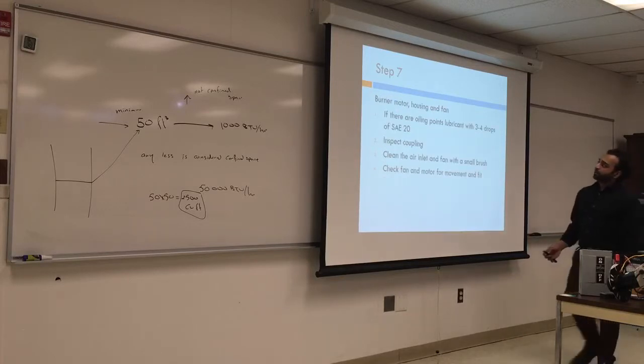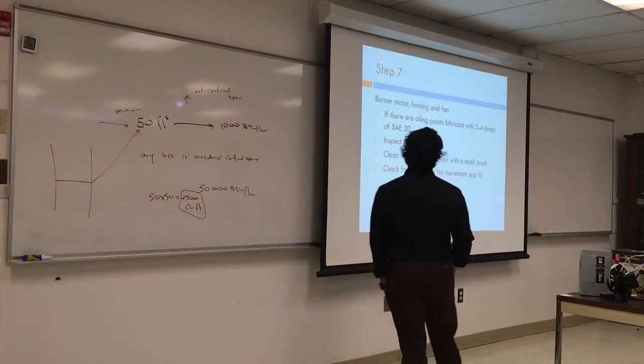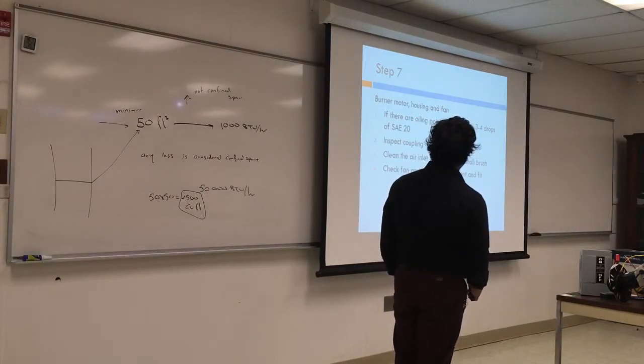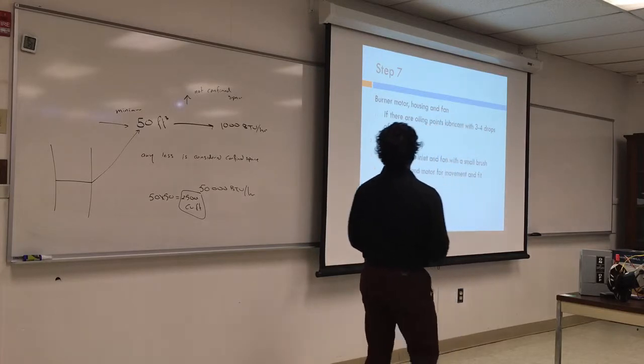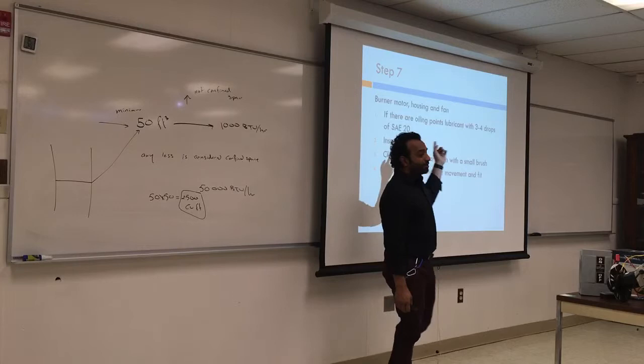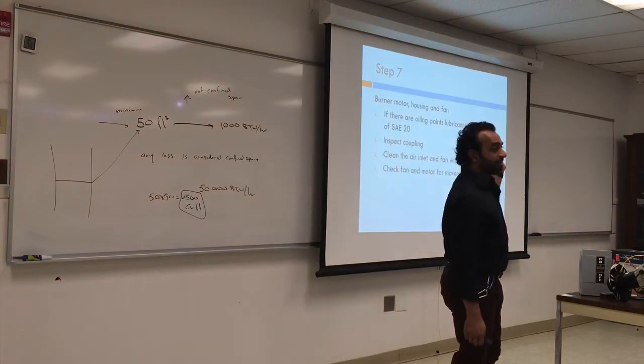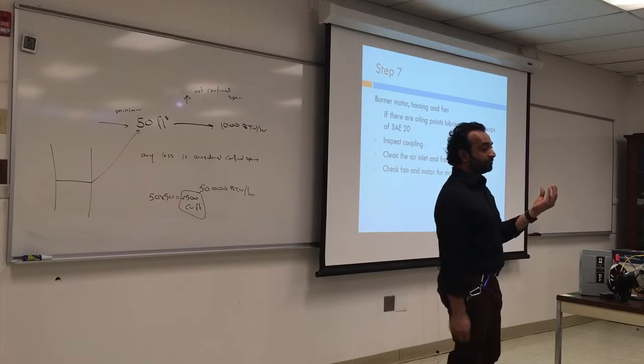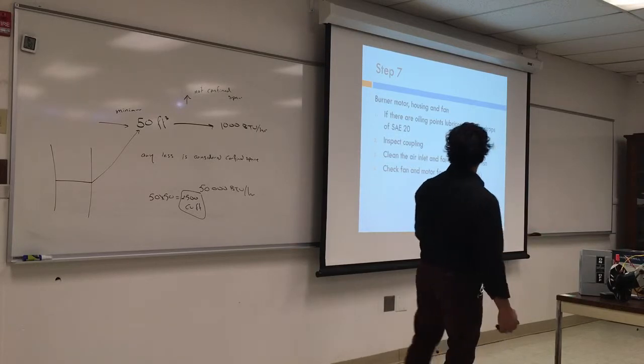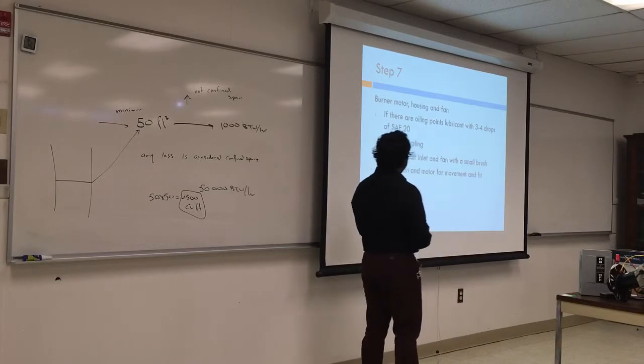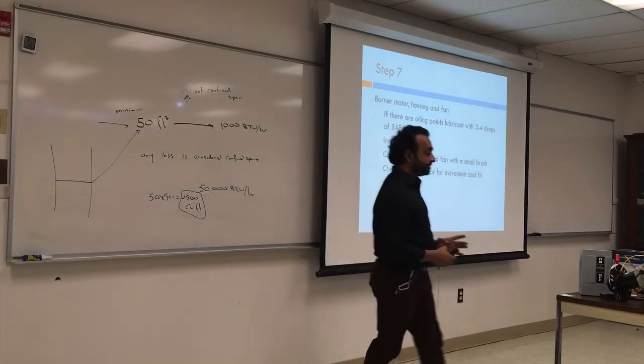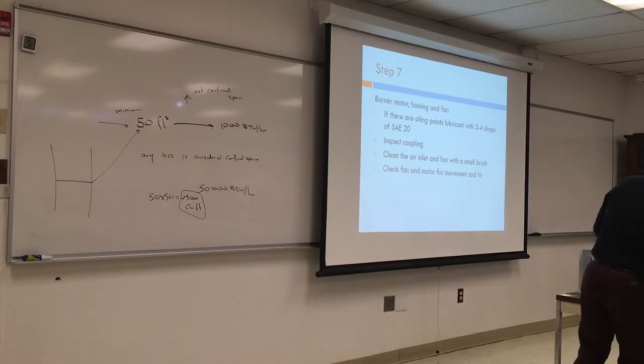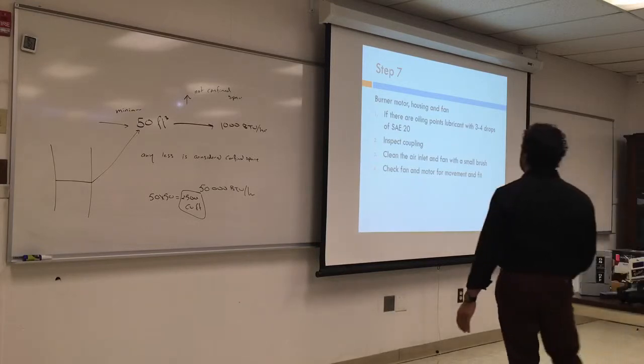Step 7, look at the burner motor, housing, and fan. If there is an oiling point, lubricate with 3 to 4 drops of SAE20. It's really old, I don't think you will see that a lot. But there's some kind of oiling point where you just put some drops of oil and you'll see some instruction on it. You'll see that actually in some burner motors and also in some inducer fan motors. Inspect the coupling. Clean the air inlet and fan with a small brush. These fans get exposed to a lot of air, so you'll see some buildup. Take them out, clean them, wash them, put them back.